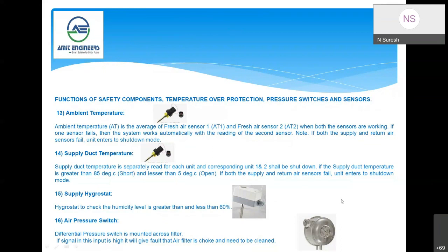And the air pressure differential switch is basically to give an alarm if there is a blockage in the filter over a period of time, so that there will be a choke in the filter. Initially the pressure difference across the filter will be less. Over a period of time, the pressure difference will increase. When the pressure reaches 200 pascals, a signal is given to the TCMS and a fault alarm is given to the operator, so that the needed maintenance can be done. This will improve the reliability of the system. If the filter is not cleaned, the needed airflow will not be there, so to monitor the pressure drop across the filter, this air pressure differential switch is used in the system.